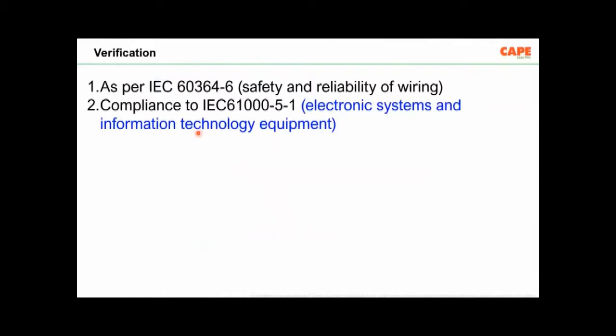Now, the last part. Whenever your electrical system is completed, we are supposed to verify the system, which includes inspection and testing. Similarly, for an electronic system, during or after commissioning, we are supposed to comply as per the IEC 61000-5-1 standard, for electronic systems and information technology equipment. After installation, we are supposed to do testing. I'm not talking about the testing of an electrical item or a device. I'm talking about the testing of the entire system, starting from probably a UPS and all the items connected on the electrical network. So this testing is also compulsory. Most of you know of IEC 60364, and 10 tests are recommended in our IS 732, but mostly we don't do it.